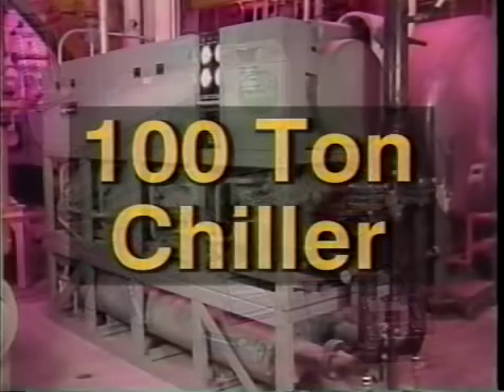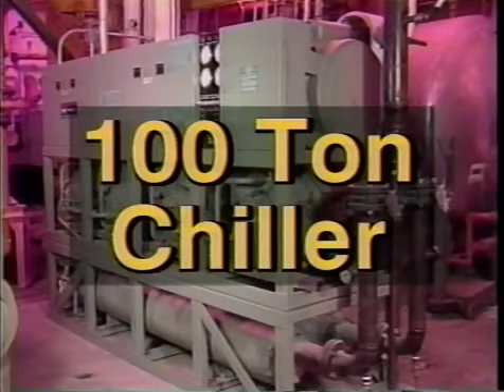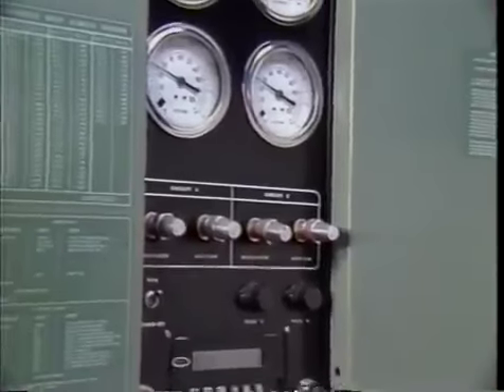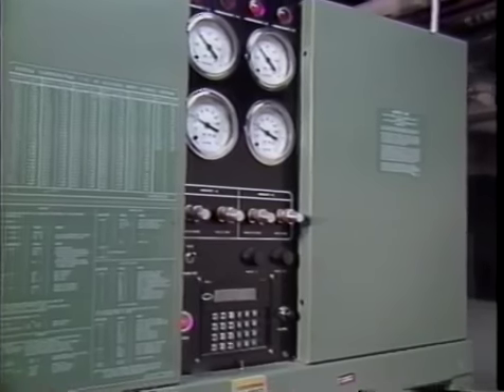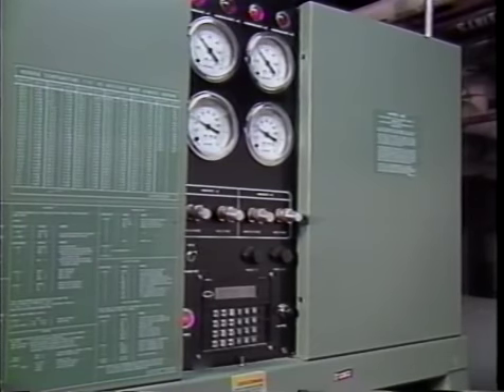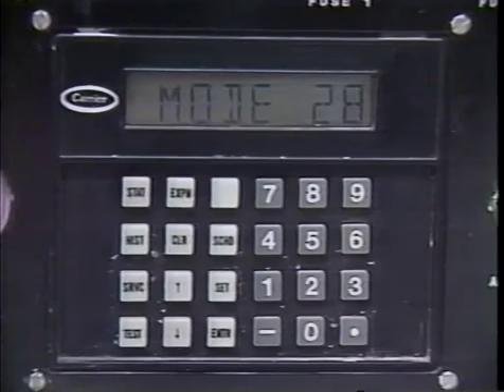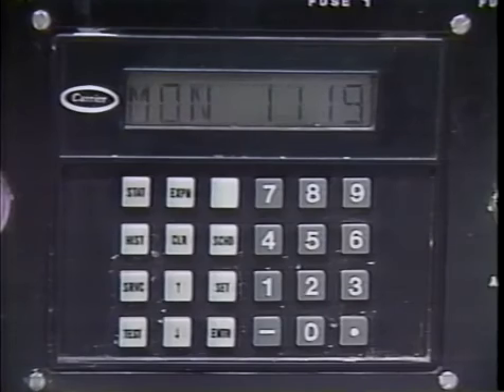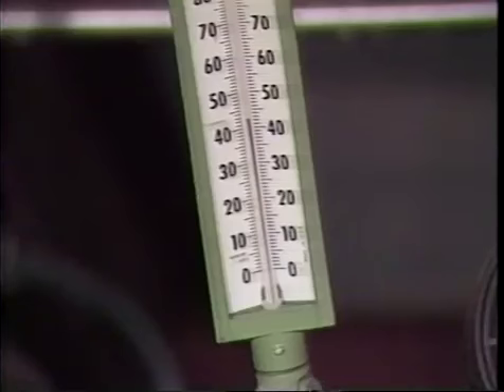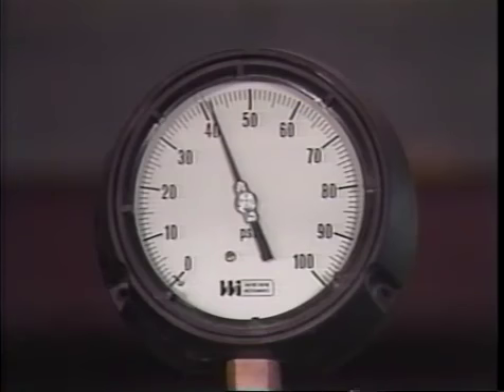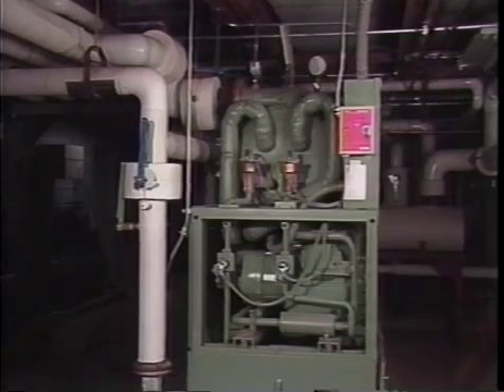Now we're going to go through a typical operational check using a water-cooled nominal 100-ton chiller on air conditioning duty. The chiller we selected has a microprocessor control system. Many of the readings needed for troubleshooting are provided by a digital LCD display. Many chillers are not provided with this type of electronic display. If that's the case, the information will have to be obtained from thermometers and pressure gauges at critical locations in the chiller system. When we are called on to troubleshoot a chiller, it's usually because the chiller cannot make capacity.